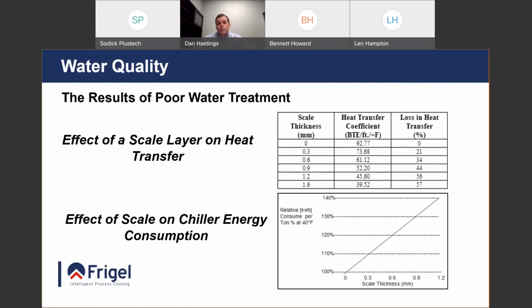So now your chillers are going to be working harder, your pumping system is going to work harder, and your machines are going to be working harder just by that little 1 millimeter layer of scale. If everything's working harder, well, maybe you have to maintain your equipment more, and you're also going to pay more energy. So by keeping water quality, and especially scale, to a minimum and keeping your tools clean, we're probably going to save money, and also it's going to affect your cycle time. If it takes 50% more with a millimeter of scale, your cooling cycle is going to be significantly impacted.